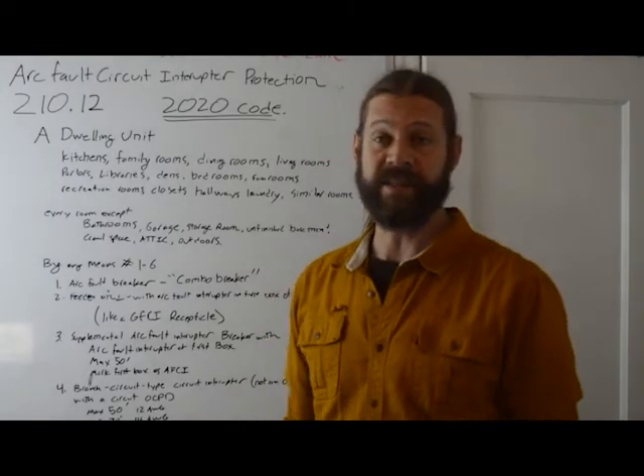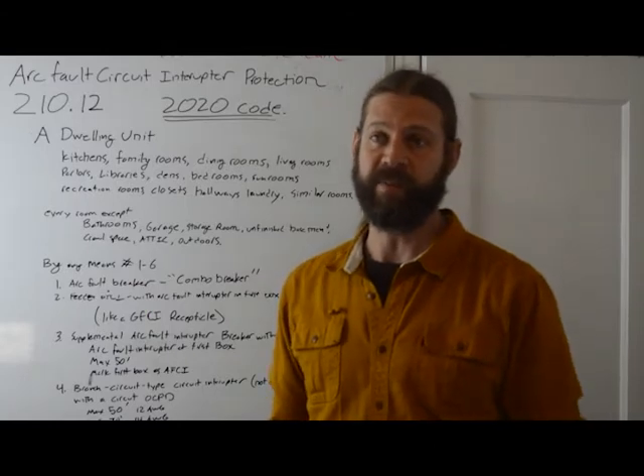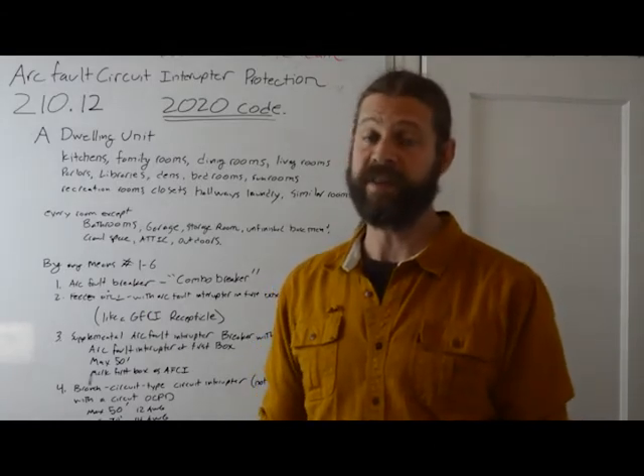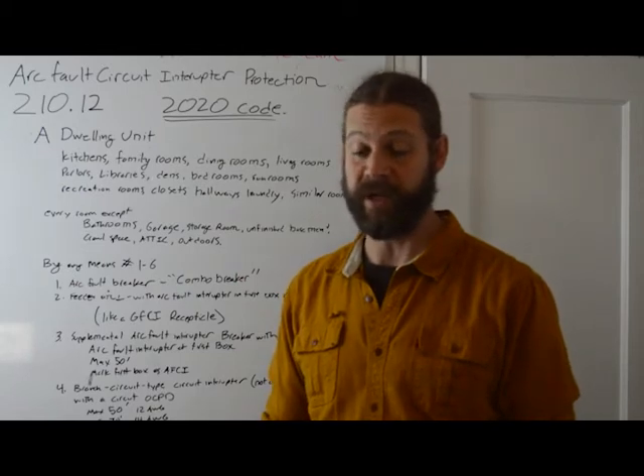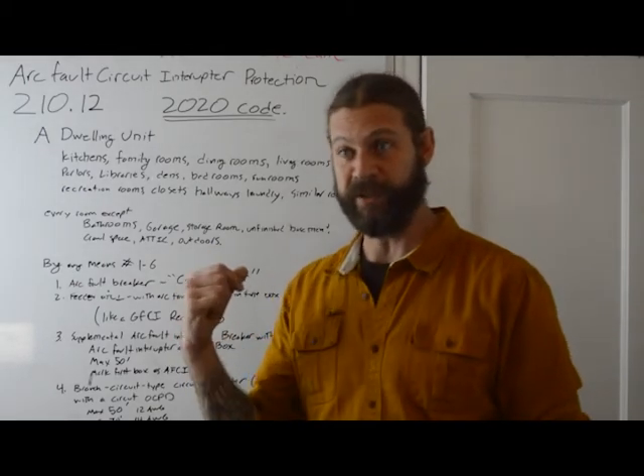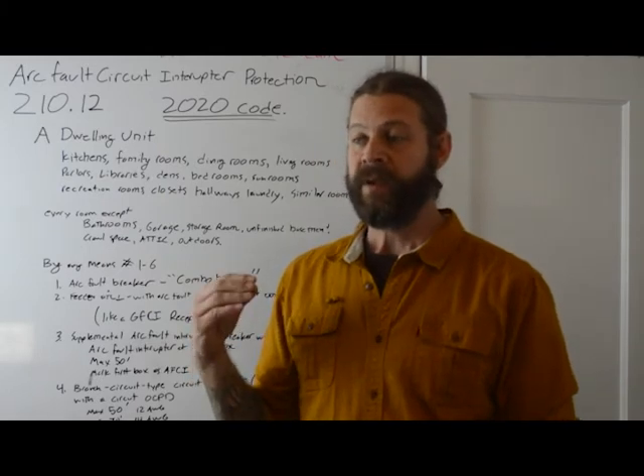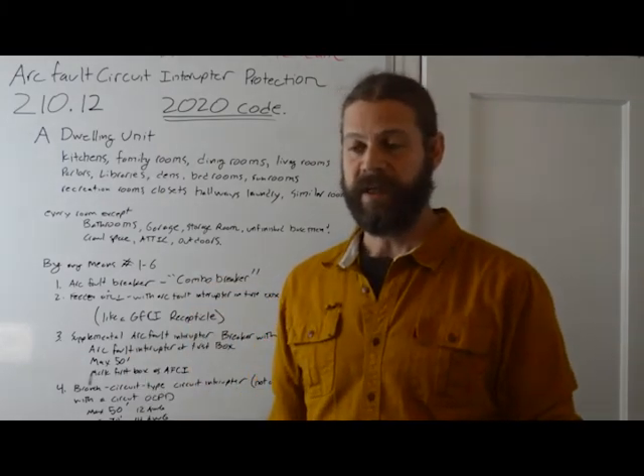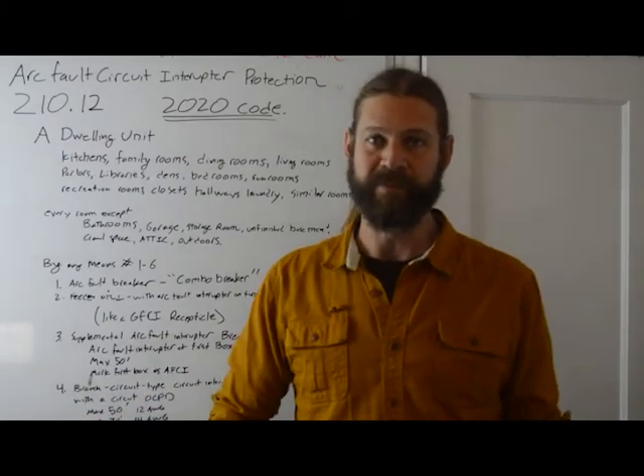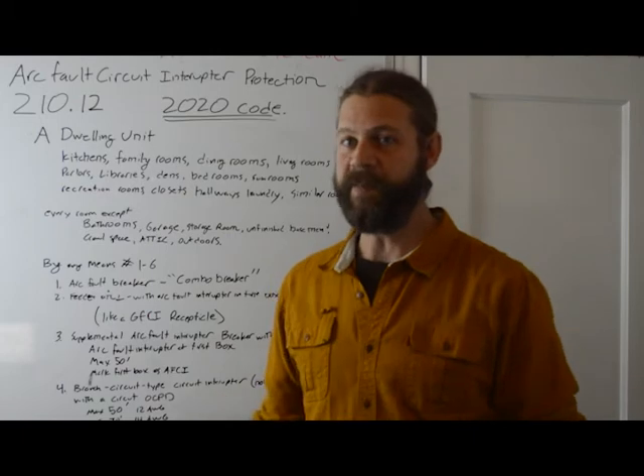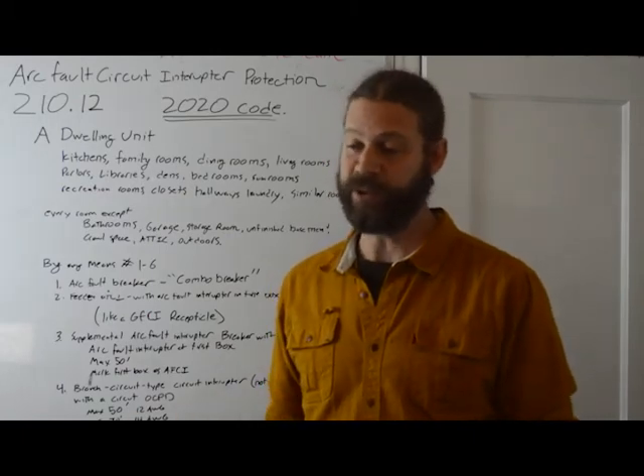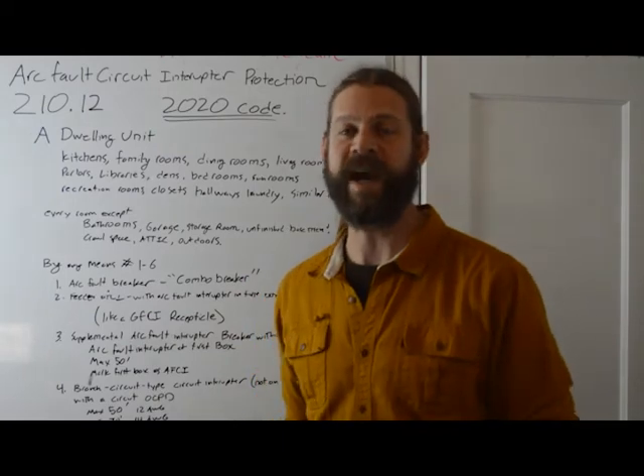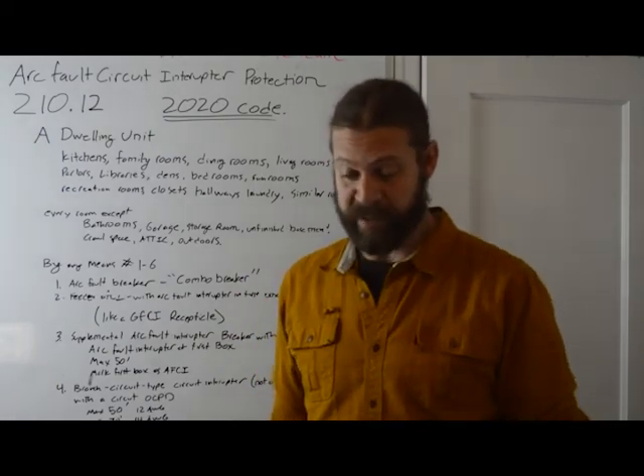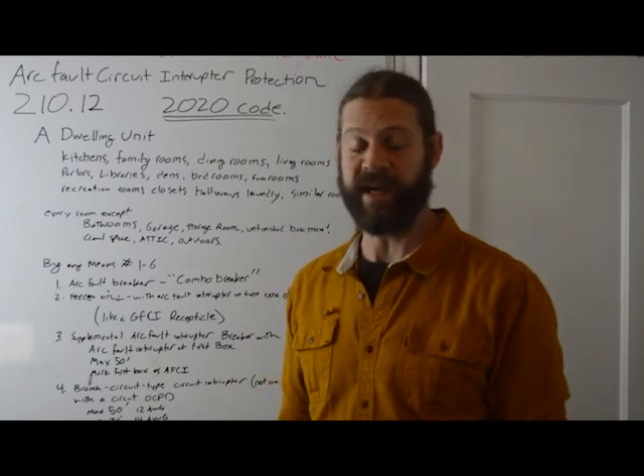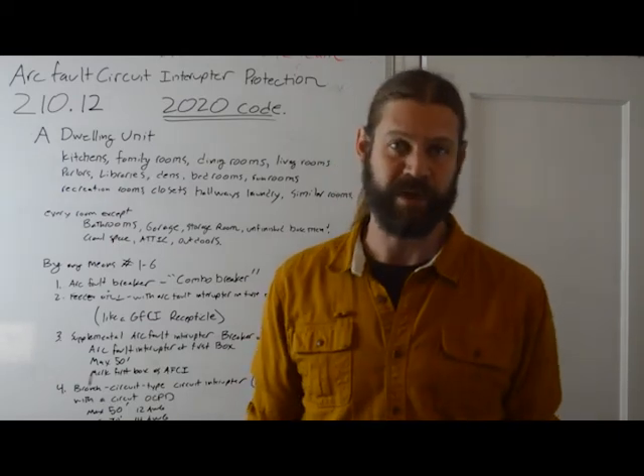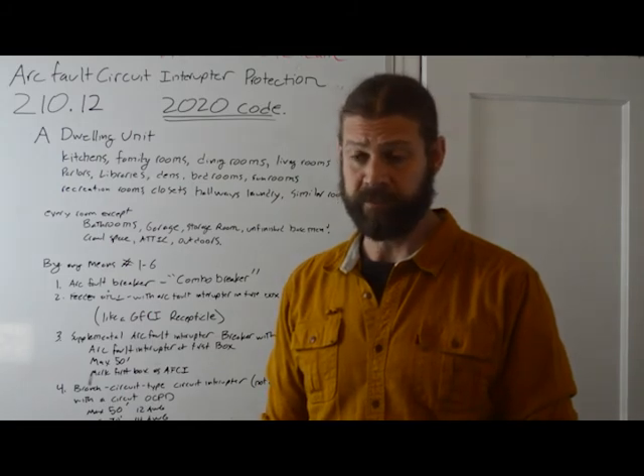So another thing that's going to jam you up is that some things produce an electrical arc as part of their regular operation. Think welders, and also think old vacuum cleaners, and also what do they call those? Surge protectors. Surge protectors are good at this. So because they can produce an electrical arc, they will trip the arc fault circuit interrupter, but that's not a bad thing. It means you should not throw away your arc fault circuit interrupter, you should throw away your vacuum. Because newer vacuums are designed to function with these arc fault circuit interrupters, and they don't create electric arcs. So that was your code for today.